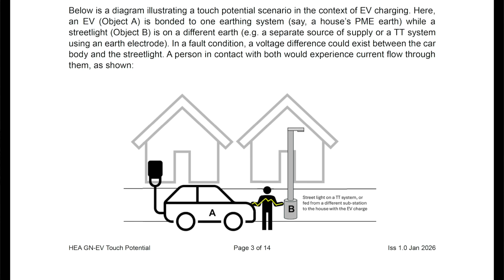Therefore, you should first aim to place all accessible conductive parts on a common earthing system so no voltage difference exists. This requires accurate information and coordination with your DNO. You also need to think about long-term maintenance to prevent divergence of earth systems in the future.